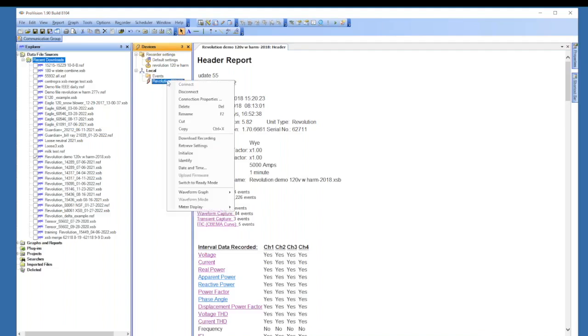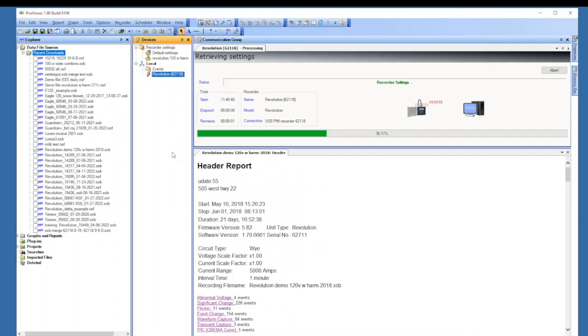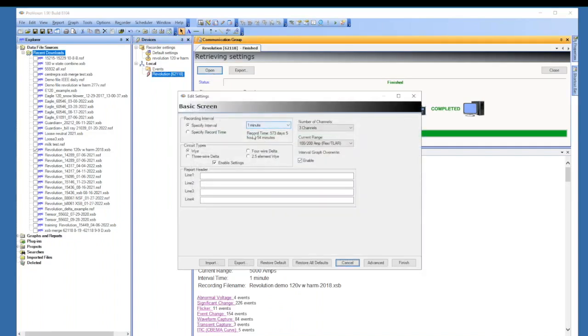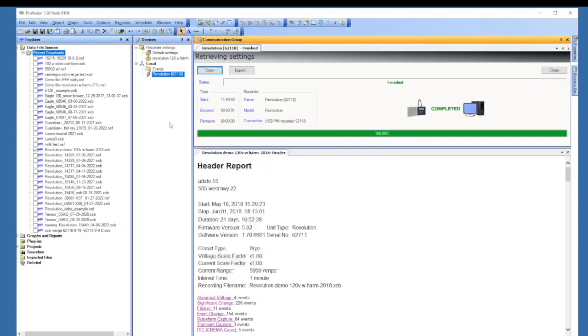Now, a template does max out, so it assumes that your recorders have the maximum memory. So what you may want to do after that is go ahead and do a retrieve settings, open that up, and then just verify that your record time is correct. And if you don't have enough record time, you can adjust it there and then cancel it. So you can have multiple templates. You can have them for different voltages with or without harmonics. If you have the Guardian recorders, you're pretty much going to be using the same setup on those. So it'd be real easy just to create a Guardian template and drop that on your Guardian whenever you need to initialize it.